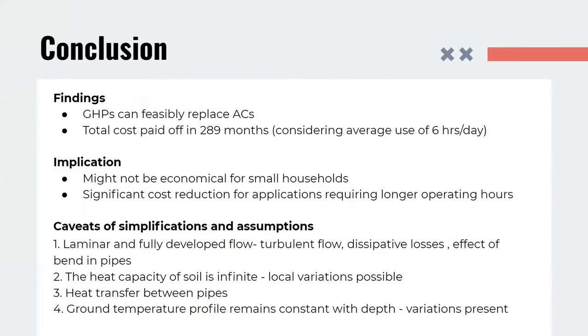Coming to the conclusion, we find that the geothermal heat pumps can feasibly replace air conditioners, and the total cost is paid off in 289 months considering an average use of 6 hours per day. This implies that geothermal heat pumps might not be economical for small households, but significant cost reduction can be achieved for applications requiring longer operational hours, such as large complexes, offices, hotels, factories, etc.